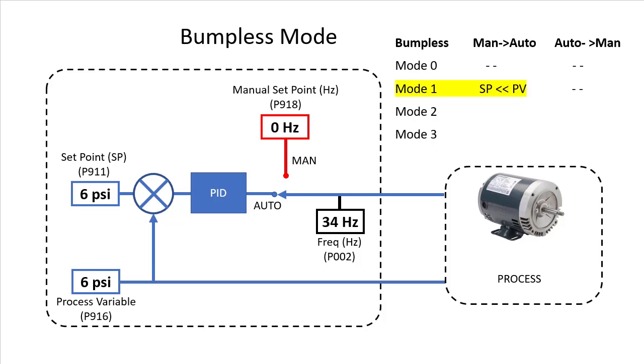Bumpless mode 1 is what we just described. The set point is set equal to the process variable upon enabling PID to prevent PID from possibly driving the motor straight to full speed.